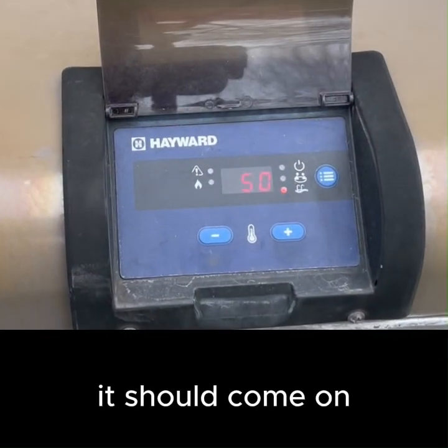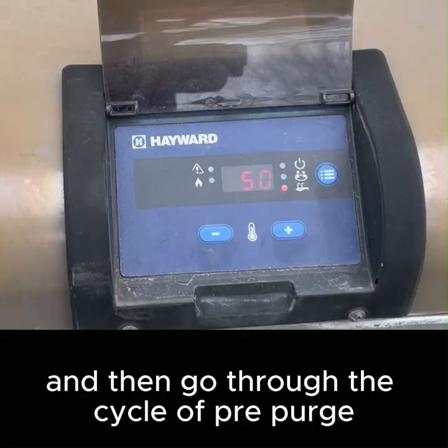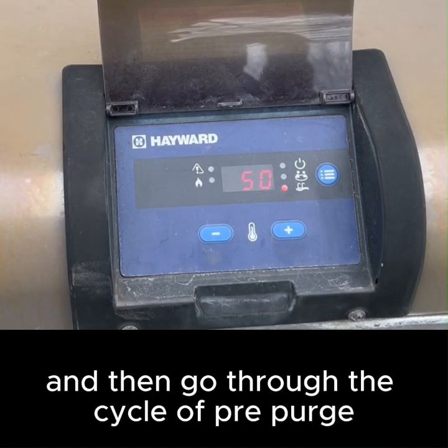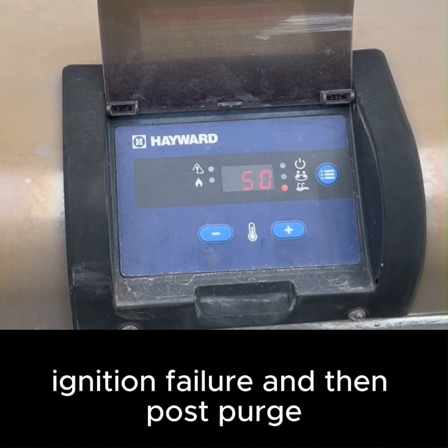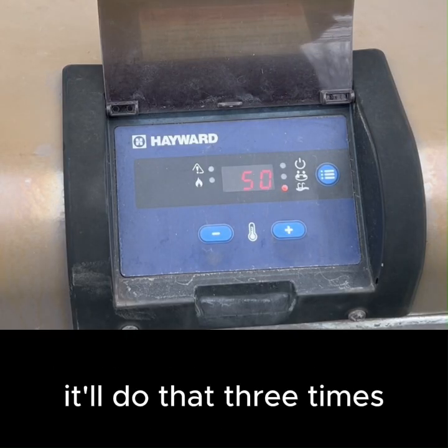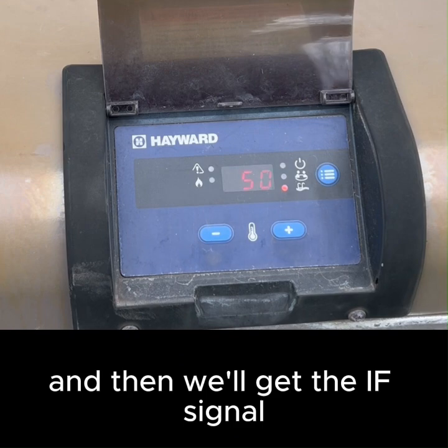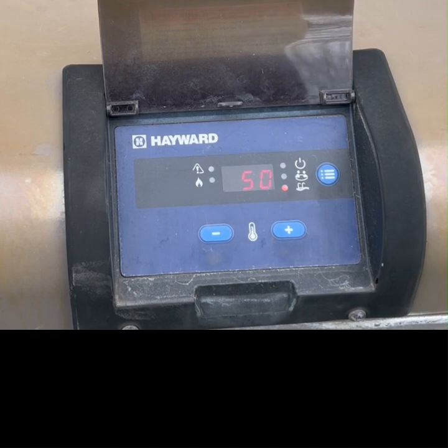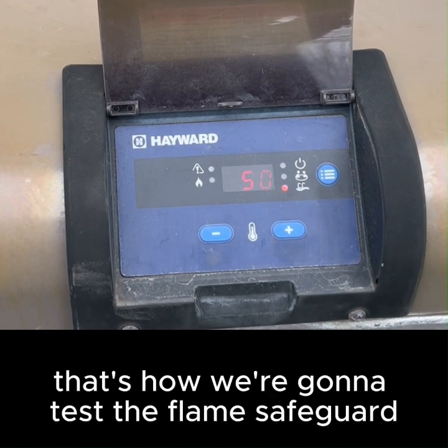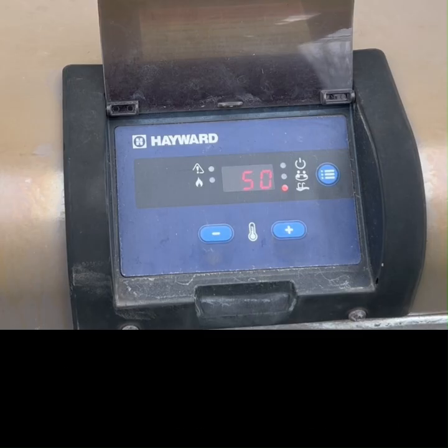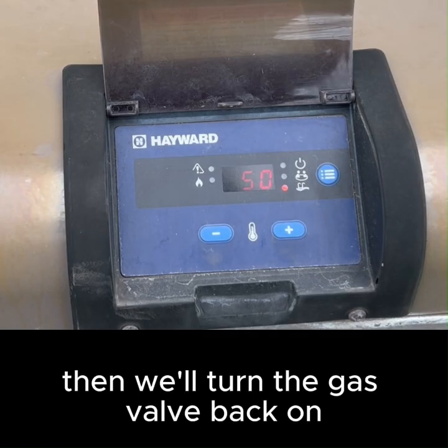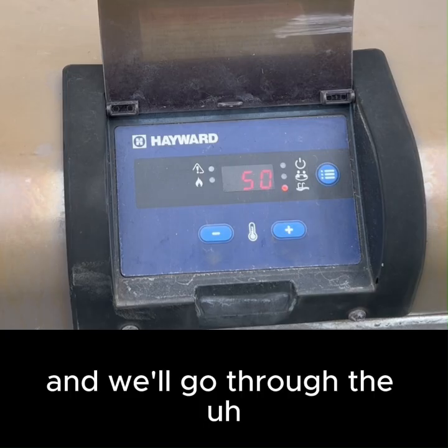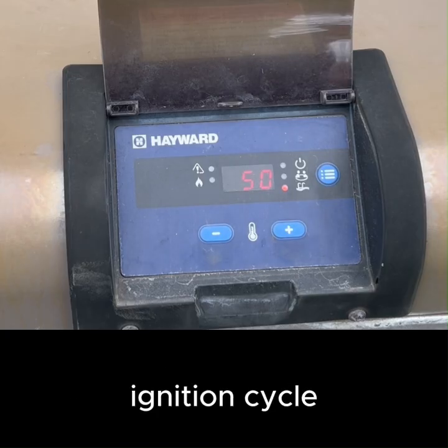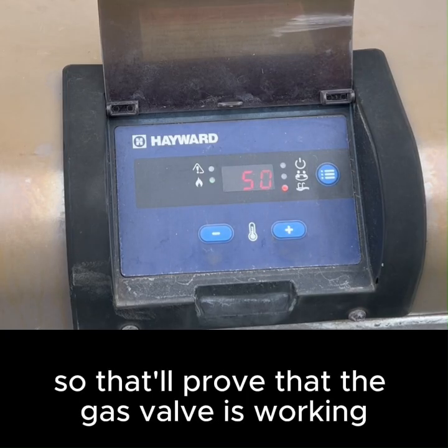And so we'll let it go through its cycle. It should come on and then go through the cycle of pre-purge, ignition failure, and then post-purge. It'll do that 3 times, and then we'll get the IF signal. And that's how we're going to test the flame safeguard. And then we'll turn the gas valve back on, and we'll go through the ignition cycle.